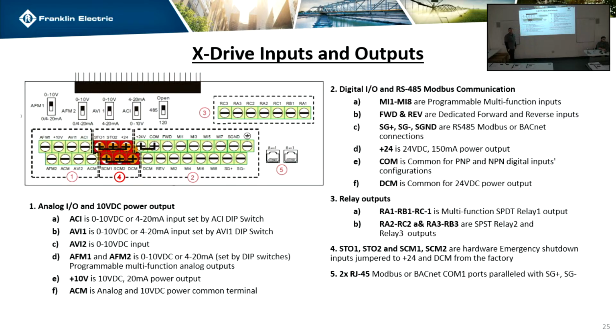Any of those are defaulted to a fireman's mode, is that correct? No, these ones are defaulted as a hardware protection, but that's used primarily for the fire suppression systems. If you see anything in a spec that requires a physical connection that shuts the drive down, that's what you're looking for. We do have fireman's override stuff in the drive that you can also program. We have inputs and stuff. Okay, separate of those. Yeah, separate of these.